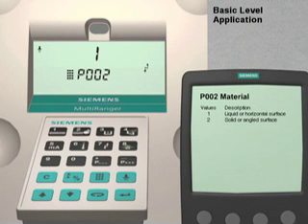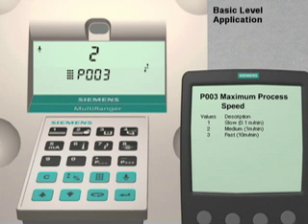Parameter number 2 optimizes the multi-ranger for measuring either liquids or solids. The factory default value is set to 1 for liquid applications. We will leave it at this value. Press the up arrow key to move to the next parameter.